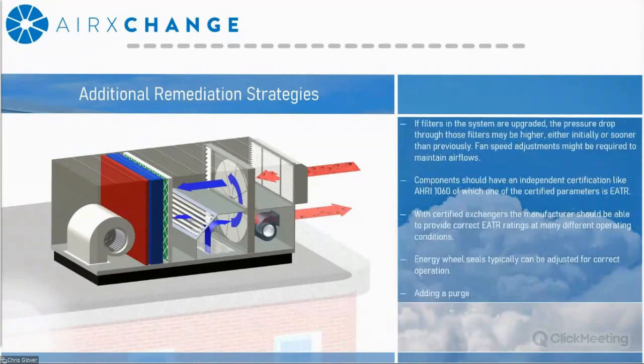All right, guys, so if replacing or upgrading filters in the system, now there's been a lot of talk about this. If you're going from a lower MERV rating to a higher MERV rating, that's going to affect the pressure drop in the system. And if you're not making any fan changes and you're just adding pressure drop, that's going to minimize the ventilation being delivered to the space.